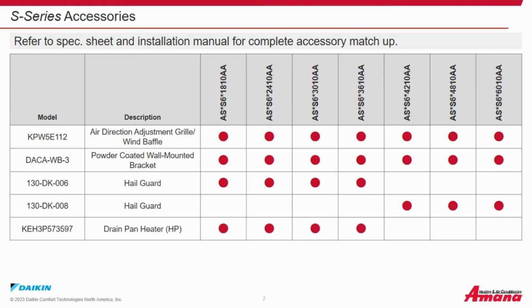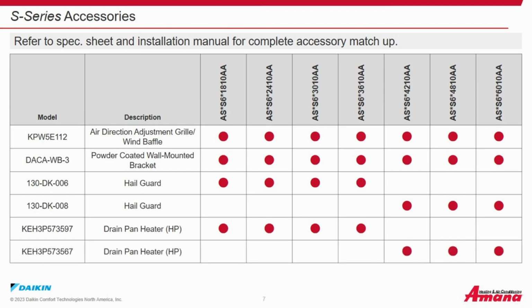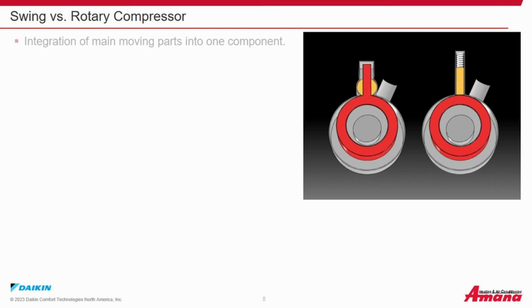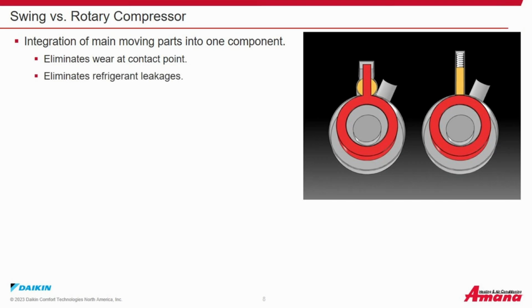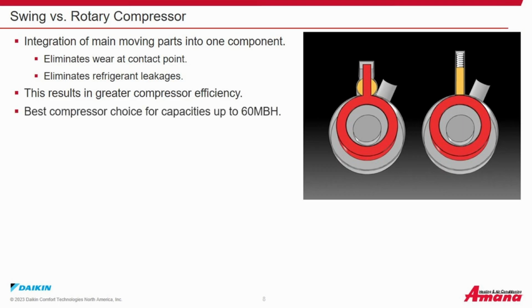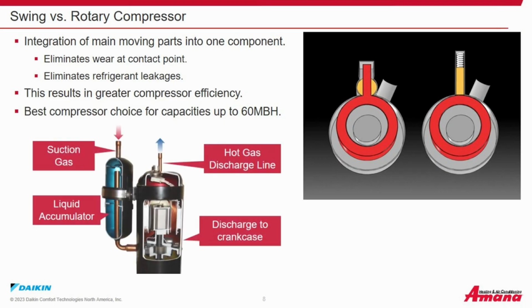The KEH3P573597 drain pan heater for the 18 through 36,000 BTU models. And the KEH3P573567 drain pan heater is for the 42, 48, and 60,000 BTU models. Swing versus rotary compressor. The integration of main moving parts into one component eliminates wear at the contact point, eliminates refrigerant leakages. The result is a greater compressor efficiency. It is the best compressor choice for capacities up to 60,000 BTUs.